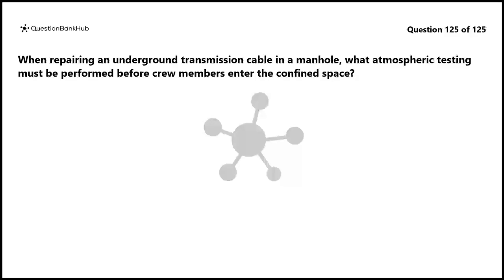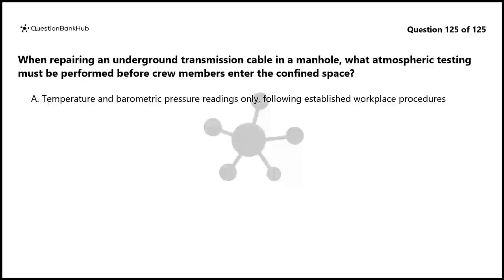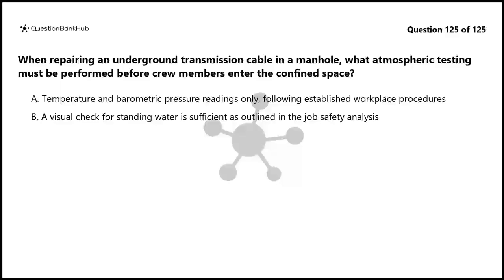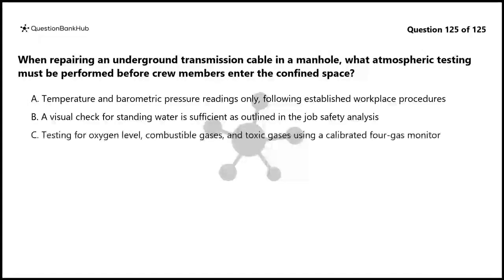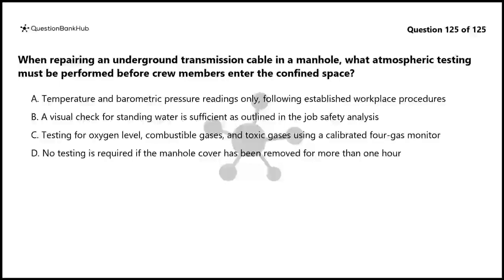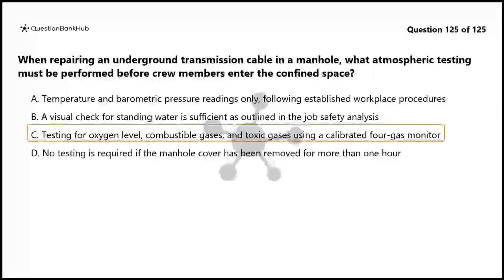Question 125. When repairing an underground transmission cable in a manhole, what atmospheric testing must be performed before crew members enter the confined space? A. Temperature and barometric pressure readings only, following established workplace procedures. B. A visual check for standing water is sufficient as outlined in the job safety analysis. C. Testing for oxygen level, combustible gases, and toxic gases using a calibrated 4-gas monitor. D. No testing is required if the manhole cover has been removed for more than 1 hour. The correct answer is C.